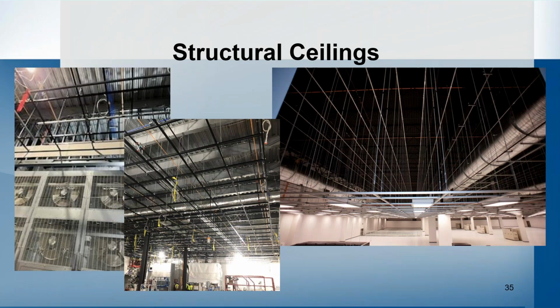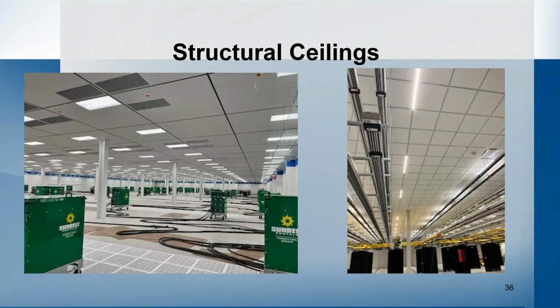So then these are just some different pictures of some different systems. I think on the right there, that's a proprietary system that's directly hung from the structure. In the middle, kind of have that strut system that's hung. So just some different type ceiling systems. And then this is what they typically look like after they close it all up. So they put ceiling panels in it. And what they do, whether it's the proprietary system or a strut system, your grid allows for them to then hang from, with the ceiling in place, hang directly from the strut or structural ceiling to hang cable trays and support cables and wires and electrical and various other things.